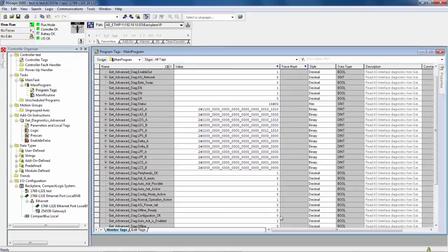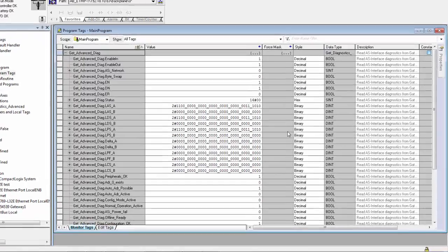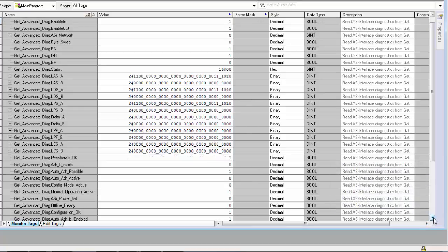So Connie will put the node 4 back on our network, and we will return to our main routine to toggle the condition. At this point, all our activated slaves, detected slaves, and projected slaves are all in sync. There is no Delta A issue, and our configuration is okay.